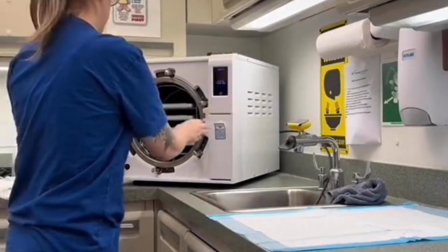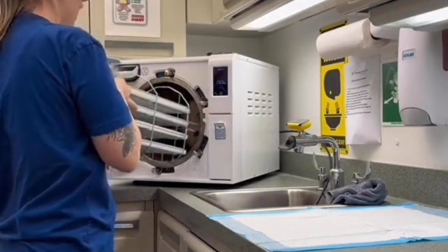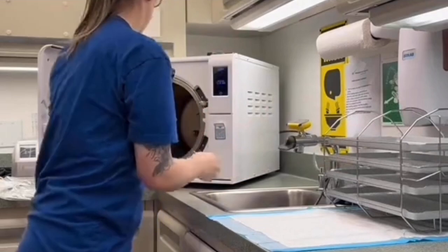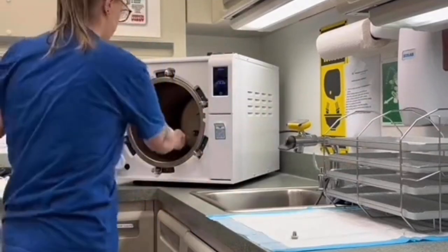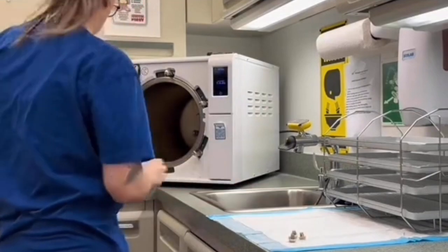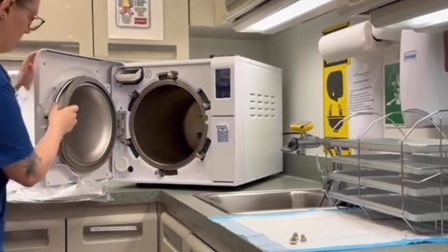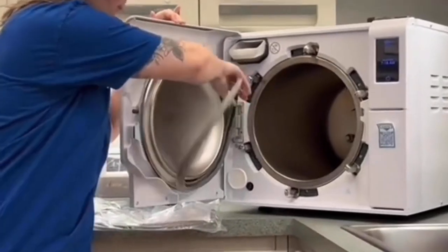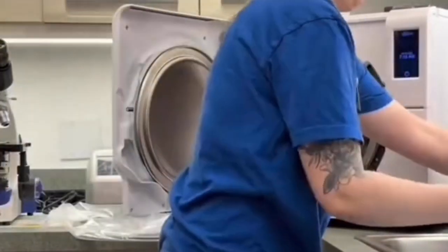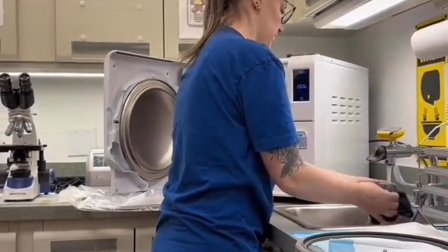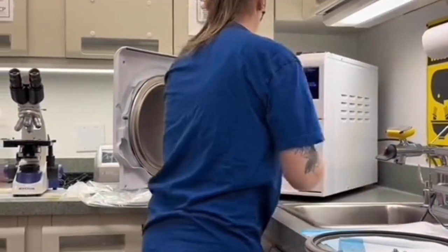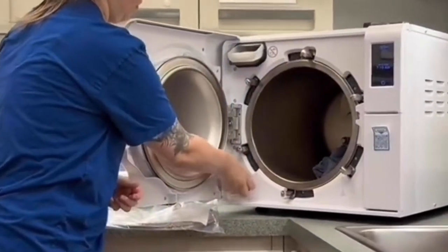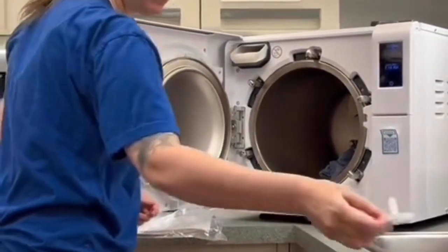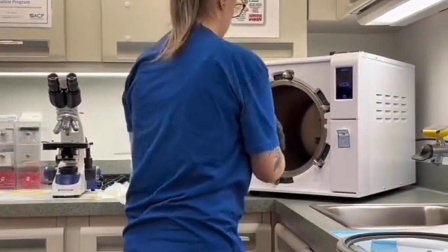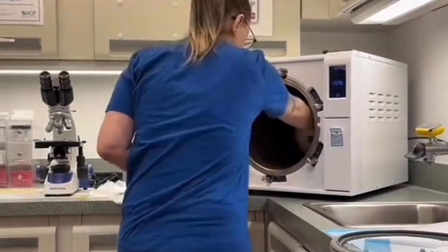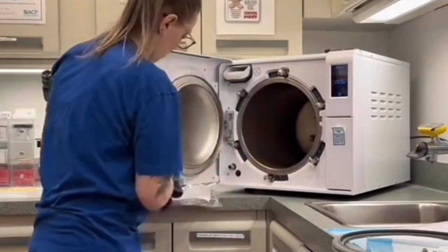Every year, or at 1,200 cycles, whichever comes first, perform the annual maintenance. Be sure to have the annual kit and a backup kit in case it is needed. Start by removing the rack and trays. Next, unscrew and remove the 3 chamber filters, followed by removing the door gasket. Finally, remove the HEPA filter. After dampening the microfiber cloth, wipe down the inside of the chamber, the inside of the autoclave, and the inside of the door.